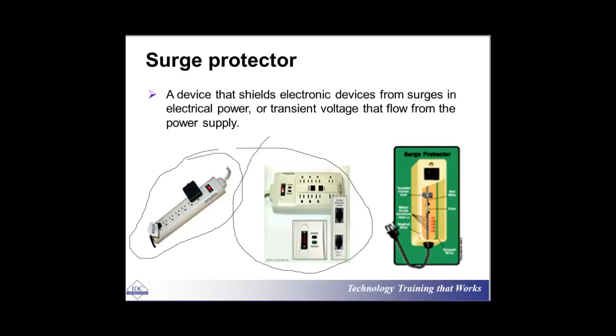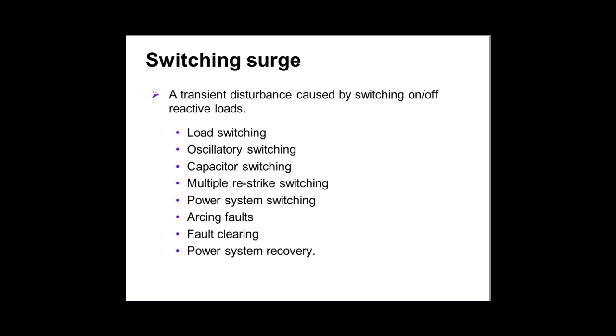Just for your information, that surge is not necessarily coming from lightning. It can be from switching operation. When they operate the circuit breakers, the big ones, it's going to make an impulse in your system. This is what we call the switching surge, which can be load switching, oscillatory switching, capacitor switching. It's going to happen all in their substation. You are innocent. You have done nothing. But the power company is doing that. Power system recovery, fault clearing, arcing faults or something. The result is that your system is down.